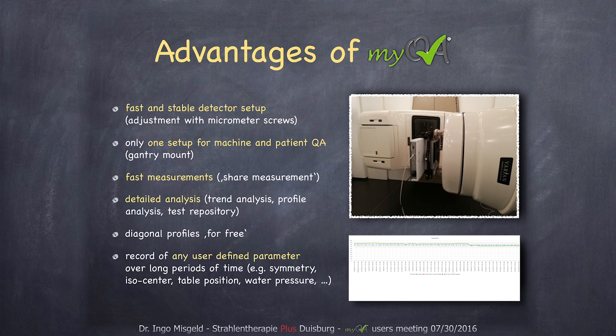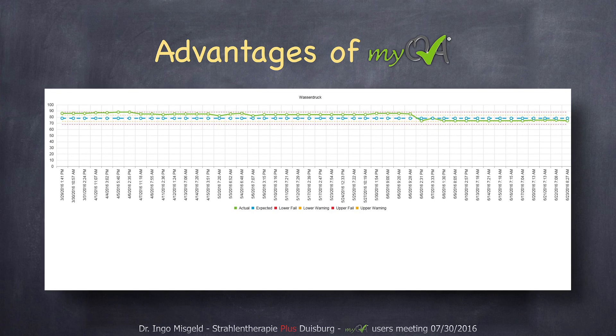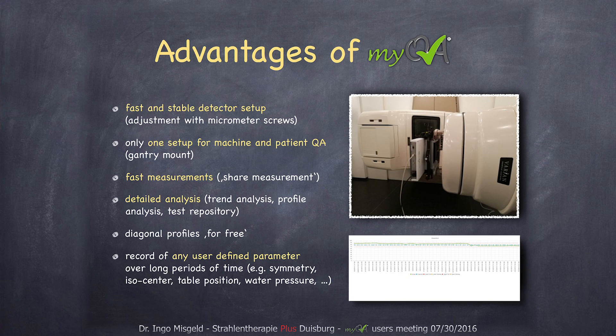You also get the diagonal profiles for free — every profile you record includes not only the parameters you set up in your test, but also the diagonal profiles automatically. And you can record any user-defined parameter over a long time — for example, the symmetry, the ISO center position, the table position, water pressure, whatever you want to keep track of. This trend analysis always gives you a good way to see how a parameter behaves over time.